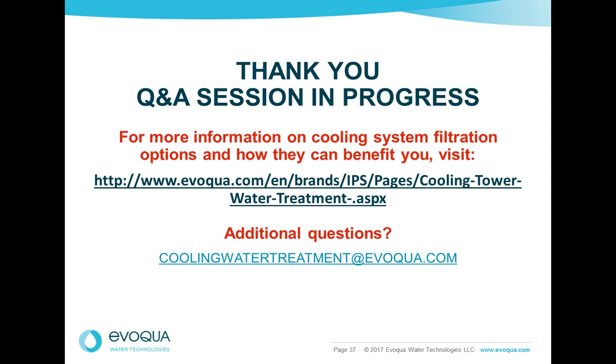This is Bob. I've seen beneficial results at 2%, but only in a very clean environment. If the wind coming by is really clean air, you might do it with 2%, but that would be the exception and not the rule. And realistically, unless you've got a huge system, going from 2 to 5 on your filter size is really not increasing the capital cost that much. It's pretty insignificant.